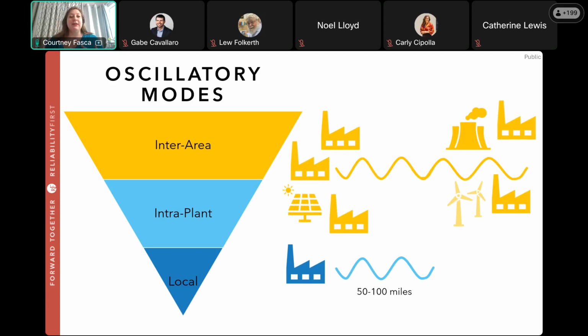These oscillations span large geographical distances, hundreds of miles, and are influenced by those transmission line impedances and tie line power transfers. So these modes typically arise from the bulk power transfer across weak tie lines connecting different regions. And when the power transfer strength or tie line strength decreases, these modes become poorly damped, and again, they spiral or oscillate out of control.